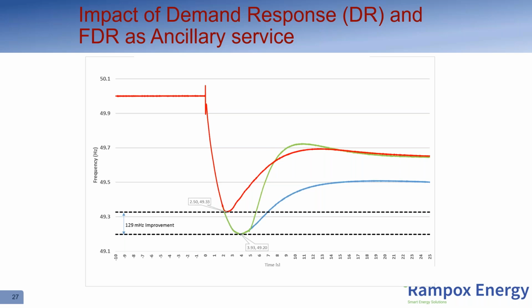The other mitigation could be in the form of demand response, which is an easy one. Demand response is basically contracting some big industrial loads—it doesn't even have to be industrial, as long as it's bulk loads. The system operator contracts them, and they will deploy them as and when the system sees fit in terms of curbing these frequency runoffs. So if a particular event happens and these loads have been contracted with proper control settings and relays next to them, they will be triggered automatically and cut off the system. That's something that happens between the system operator and the customer.